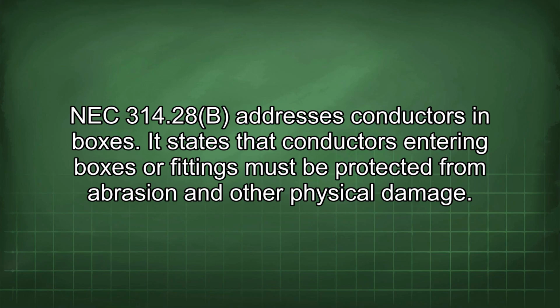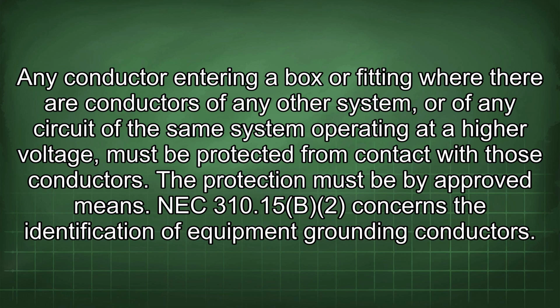NEC 314.28(B) addresses conductors in boxes. It states that conductors entering boxes or fittings must be protected from abrasion and other physical damage. Any conductor entering a box or fitting where there are conductors of any other system, or of any circuit of the same system operating at a higher voltage, must be protected from contact with those conductors. The protection must be by approved means.